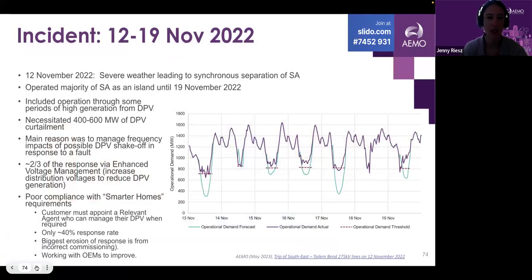This example here is talking about an incident that we had just in late 2022. There was severe weather around the interconnector that led to a separation event and South Australia operating as an island. Because of damage to the transmission lines, it was operating as an island for about a week, from the 12th to the 19th of November. And that included operation through some periods of extremely high levels of distributed PV operation. We had to curtail this. This was using our ability to curtail PV in practice for about a week.